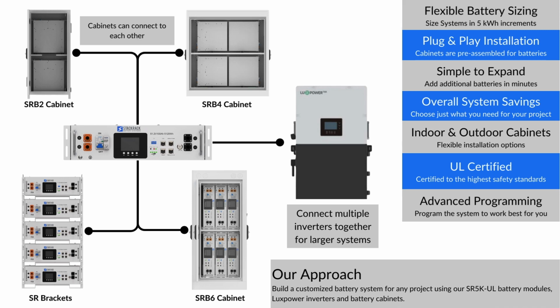Highlighting what this system can provide. On the right-hand side, you get flexible battery sizing in 5 kilowatt hour increments. This is a plug and play installation architecture. The battery cabinets are pre-assembled. It's very simple to slide modules in. It's simple to expand battery banks. You can add battery modules at any time. It's very simple to connect battery cabinets to one another through the bus bar system.